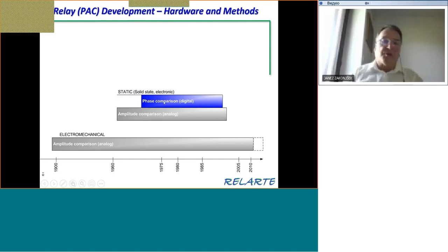A little after 1960, we came to static, solid-state or electronic relays. We called them static relays because there was nothing moving inside, unlike electromechanical relays, but they generally operated from the very beginning as analog comparison relays. Later on, around 1968-70, we came to so-called phase comparison, or what was called at that time digital relays. I will try to show you a bit later why they were called digital relays.